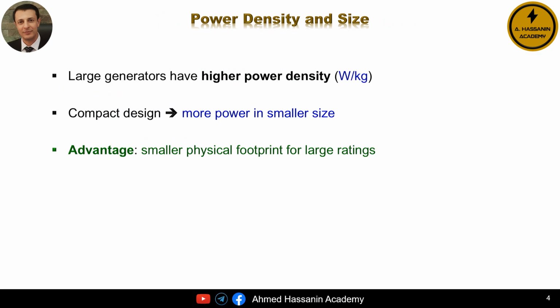Now let's move on to power density and generator size. When we deal with large synchronous generators, we're not just increasing the power rating, we're also improving what we call power density, which simply means how much power we get per kilogram of the machine. As the generator size and rating increase, this value goes up.